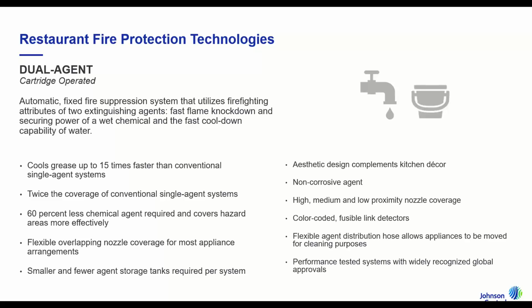The other technology to touch on is a dual agent, and this system for ours is called the Piranha system. It essentially operates very similar in relation to the fixed nozzle piping, the pull station for manual actuation, and then the fusible links for automatic actuation. What's different about it is it has the standard wet chemical agent that discharges first and is immediately followed by water for cooling. This relates to a 15 times faster cooling than a conventional single agent wet chemical system.